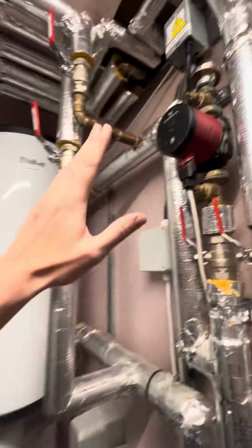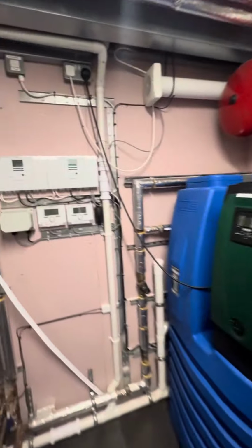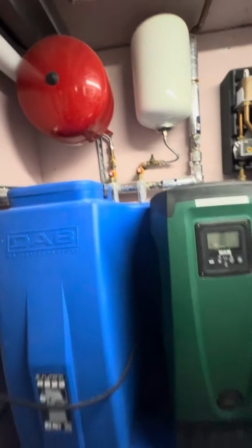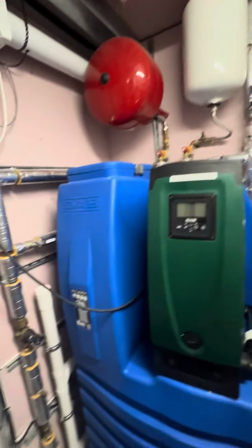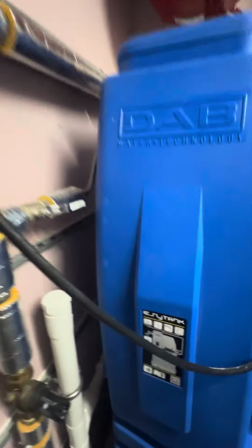But these towel rails are dual fuel, so we've reduced the heat curve from 1 to 0.4, turned the room stats all up to maximum, and the heat curve of 0.4 maintained 21 degrees throughout. So that will be much more efficient. Now, the hydraulic circuit here is also, I would say, over-engineered and not as efficient as it could be. Whether it's worth changing or not is another question at this stage, but I thought I'd explain it anyway.